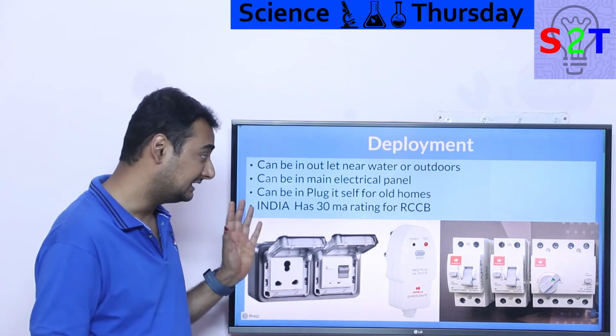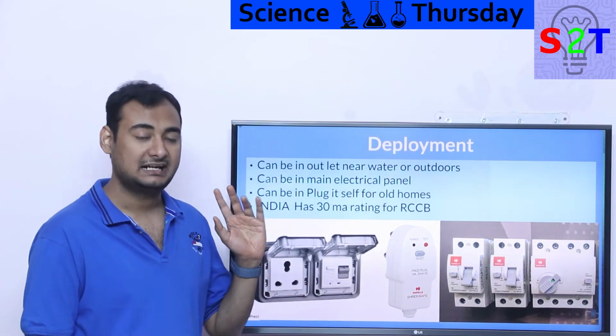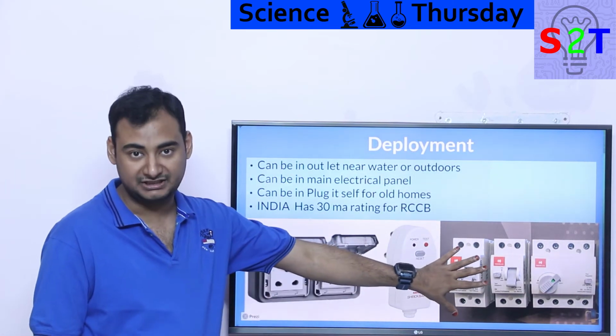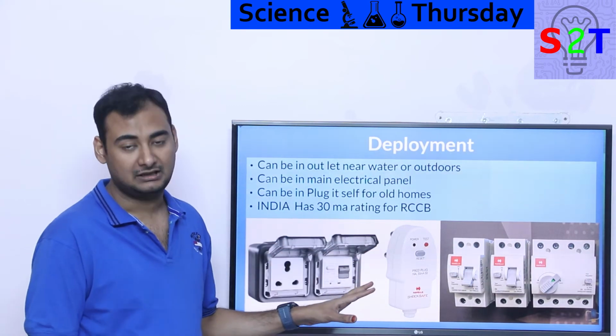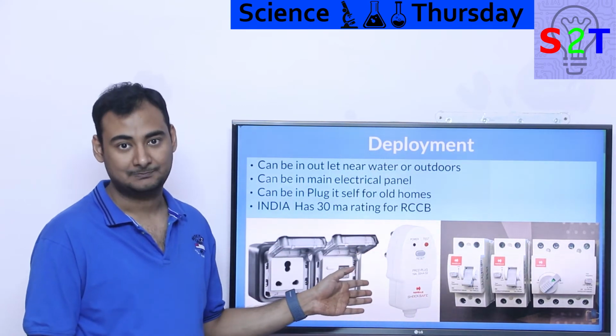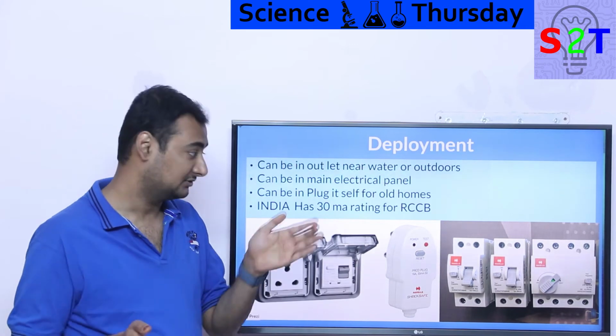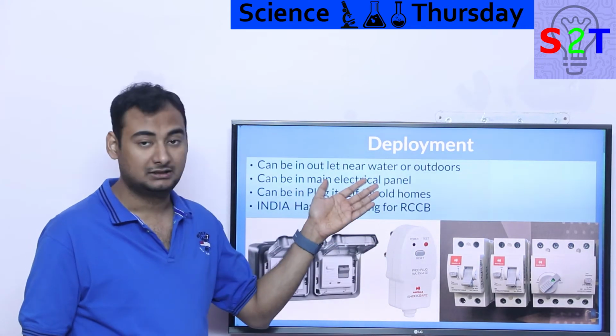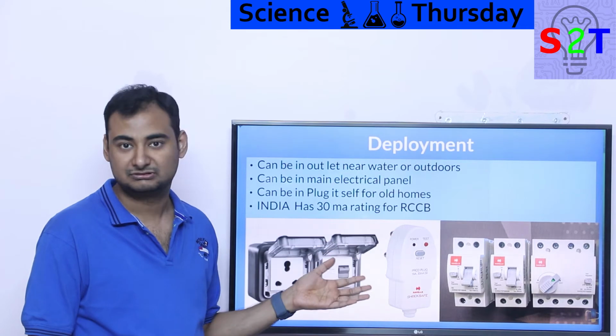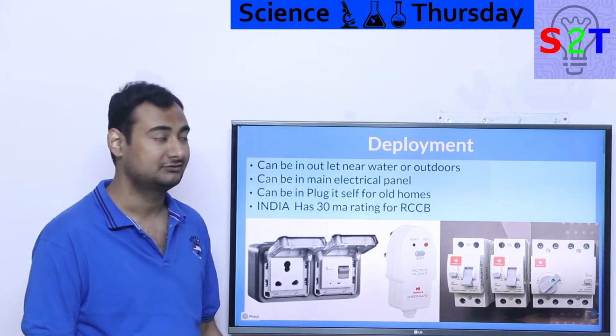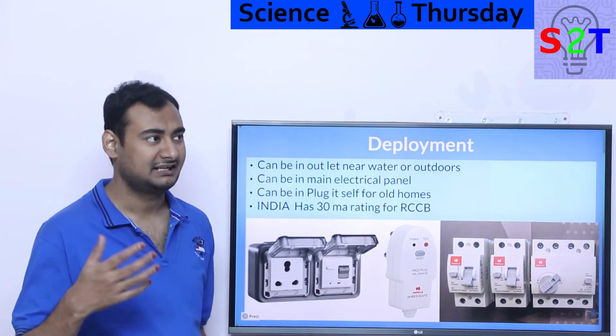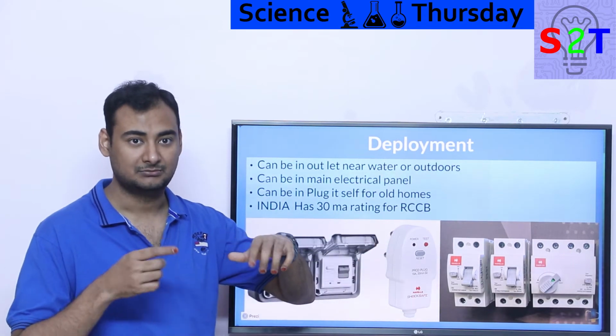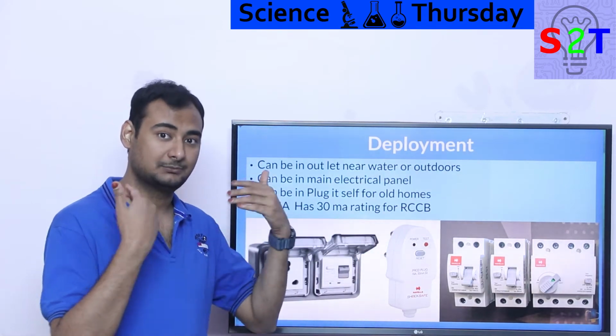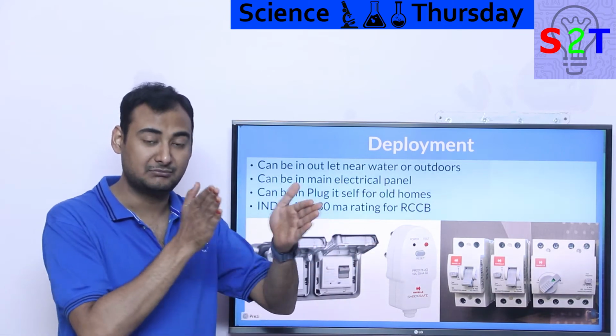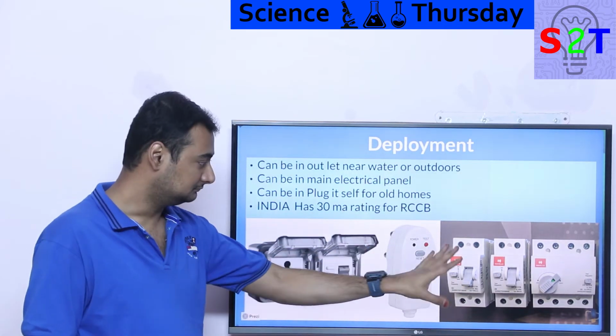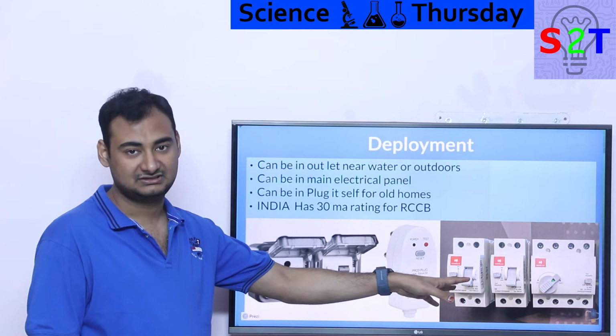That's the hope, and that's why generally you will always hear people say at least have two layers of it. One layer in your main distribution box, and second, if you have something heavy and energy intensive, please have the plug also. You never rely on one equipment itself, because A, it could fail, B, you could have a scenario where something bad has happened on the equipment end itself. So you always want multi-layer protection. It's like how your car has a crumple zone to protect you, but you're still supposed to put on a seat belt, you're still supposed to rely on the airbag also. That's the same point. You have multi-layer security. So have MCBs, have this ground fault detection.